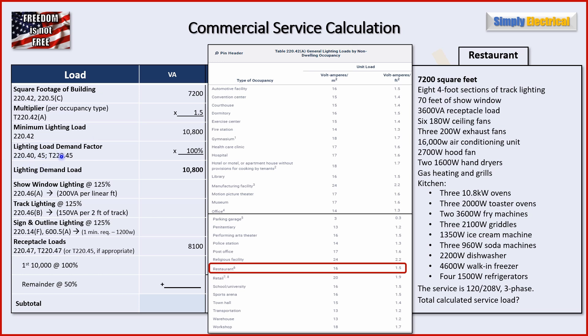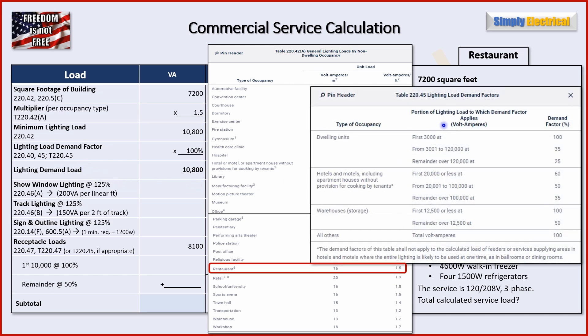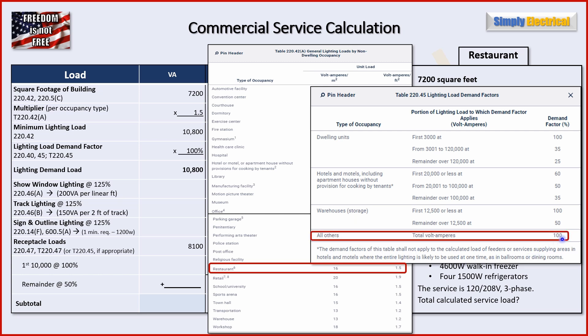Now we get our lighting load demand factor from Table 220.45. That table has four sections: dwelling units, hotels/motels/apartment houses, warehouses, and everything else. Our restaurant doesn't fall into any of the specific categories, so we go with 'all others,' which tells us we have to take 100% demand factor — we get no break for a restaurant. So our lighting demand load remains 10,800 VA.